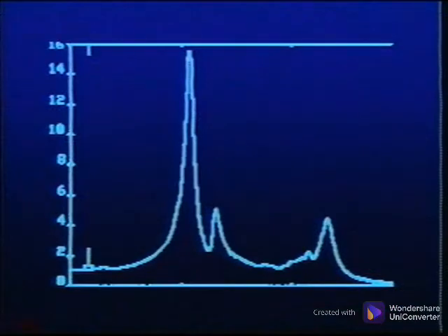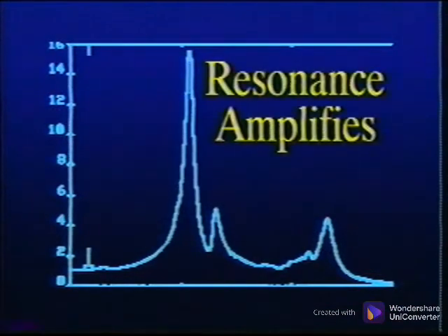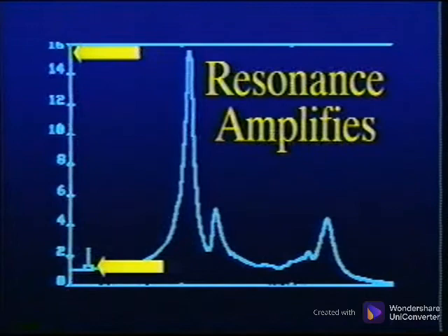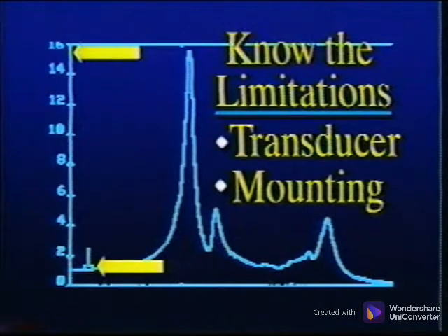The effect of resonance on your data is that vibration frequencies that occur in the resonant frequency range of the transducer will be amplified by as much as 20 times. Therefore, it is important to know the limitations of the selected transducer and the manner in which it is mounted.